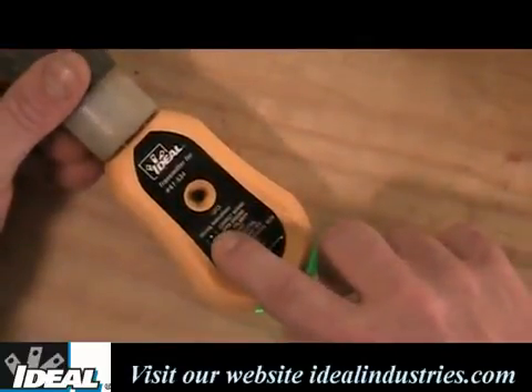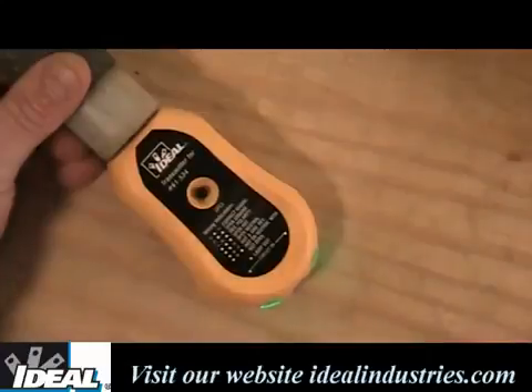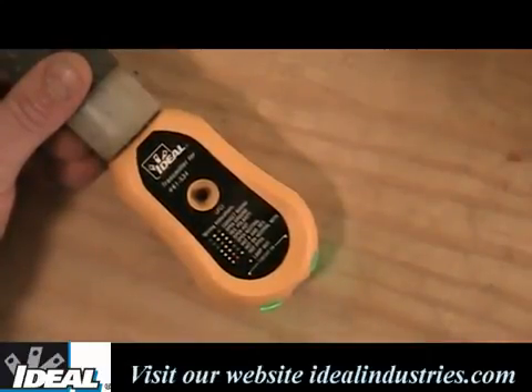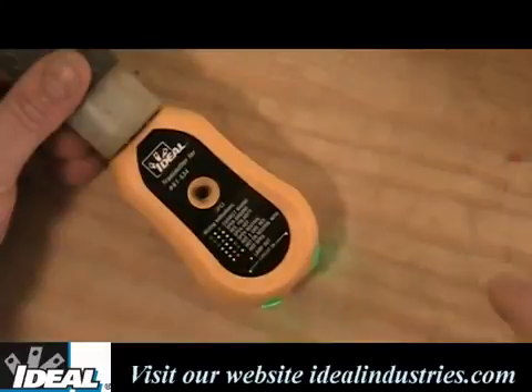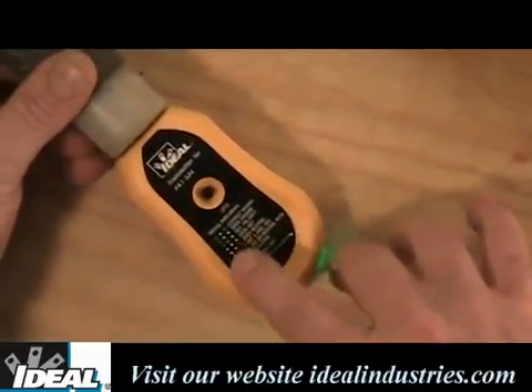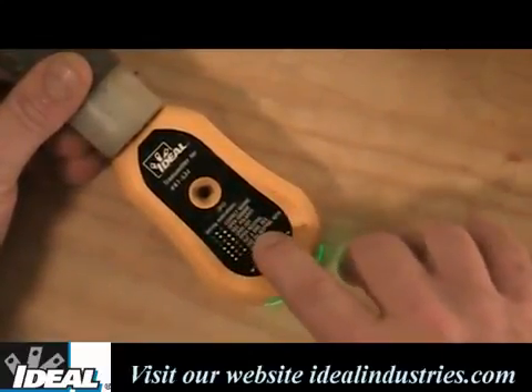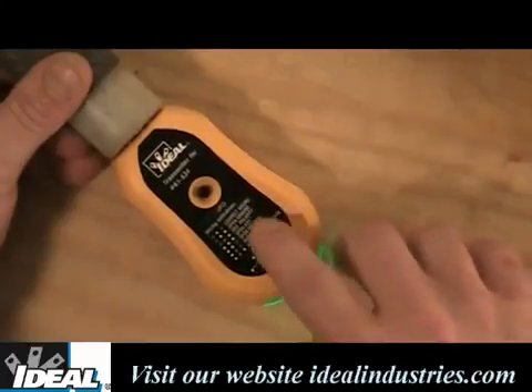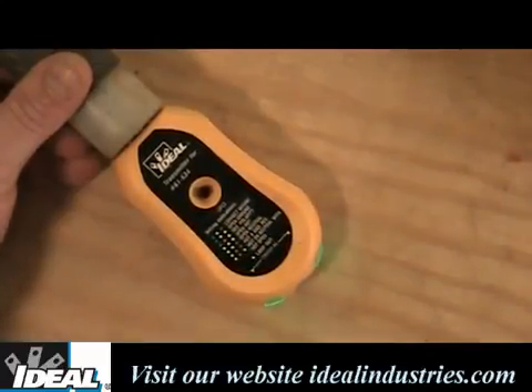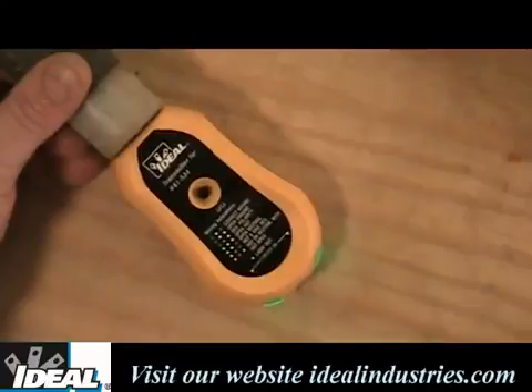If you look at the top light here, that's what indicates correct wiring. If you have any other combination of lights lit up, you might have a missing neutral, a reversed hot and neutral, or a missing ground. The combination of lights that light up will tell you what the miswire is. A lot of guys use these to trace and make sure the electrical wiring is correct at the outlet in the room.